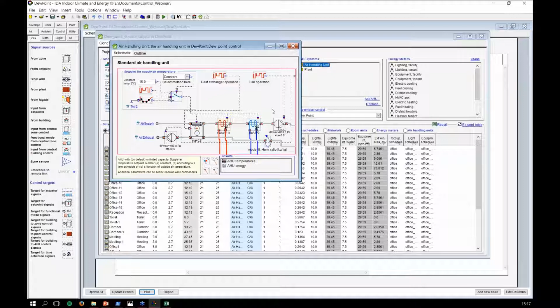So one way to avoid this is, again, to the rescue, our zone sensor. Here I'm still exporting to the plant my dew point temperature control, but instead of having a linear segmenter taking its signal from the air handling unit sensor, I'm using my zone controller to log all the zones that are connected to the air handling unit. So I take all zones connected to the air handling unit, and in this pop-up window, I choose dew point temperature. And I'm taking here an average over volume. Now, maybe this is not the best thing. Maybe average over flow rate is a little bit more important, or some might want to take the minimum of the dew point and do a control on minimum. But I'm taking this signal, and then I'm adding 1, so I'm keeping 1 degree above that dew point temperature signal.